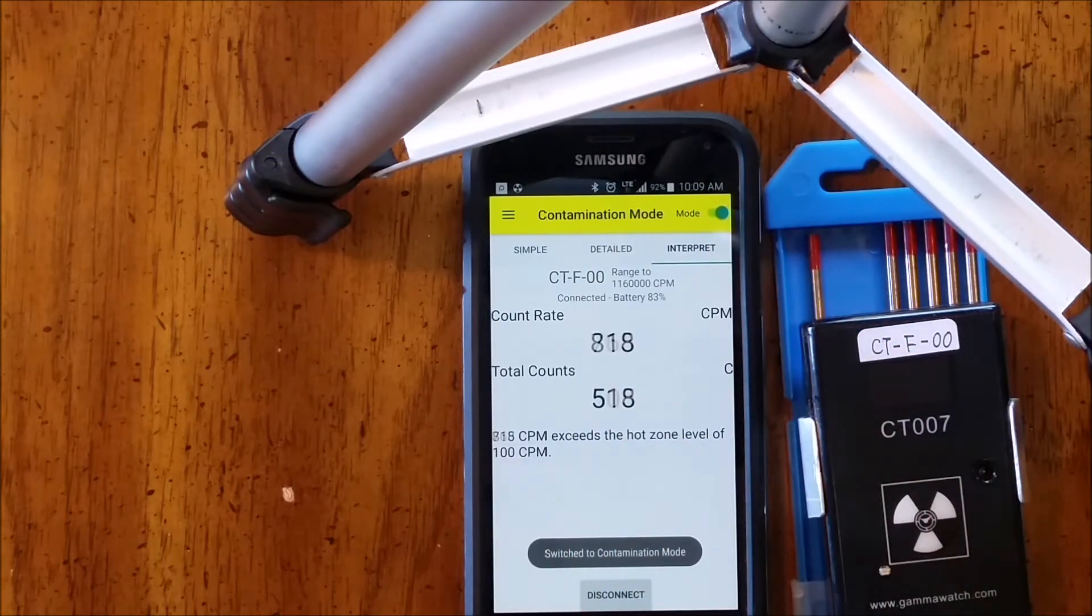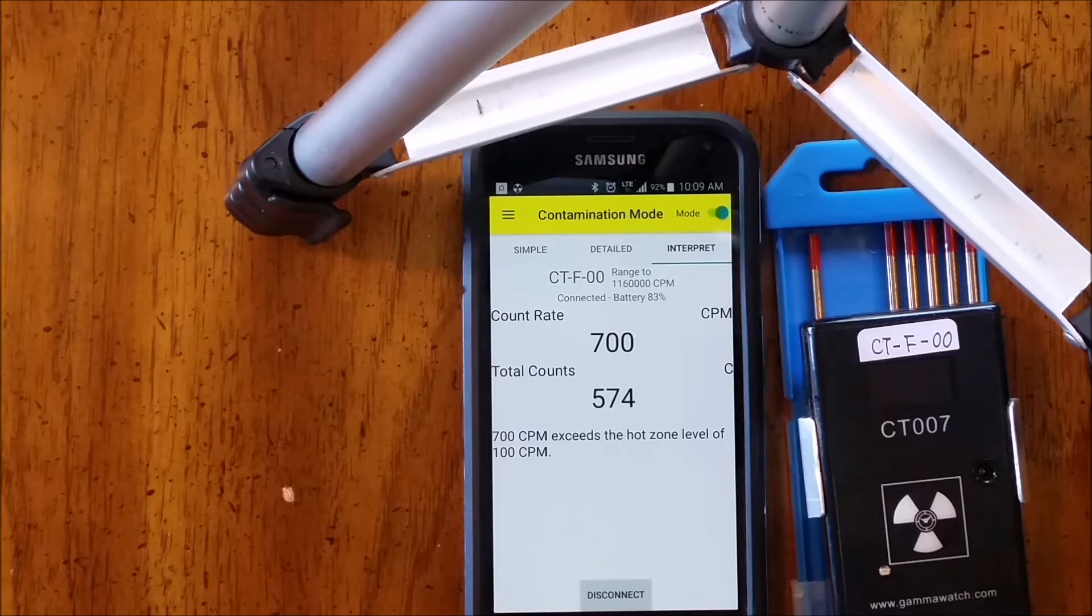And in contamination mode, it tells us that this would be enough loose contamination that we should worry about spreading this around. It says it's exceeding our level of 100 CPM. In the settings menu, we can change the units.